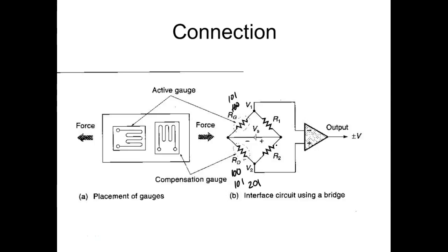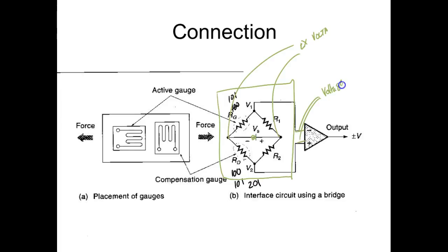So we have these things called strain gauges. This is a strain gauge, guys, right here. If you've ever looked at the print of a strain gauge, this is it. And they have two wires coming out. This is going to be for what they call the excitation voltage. Then you're going to have two wires coming out that are going to be a voltage that represents your weight. And then this output, you're saying, well, it's going to weigh the weigh bridge. Well, what you do is you compensate for the weigh bridge inside the indicator.